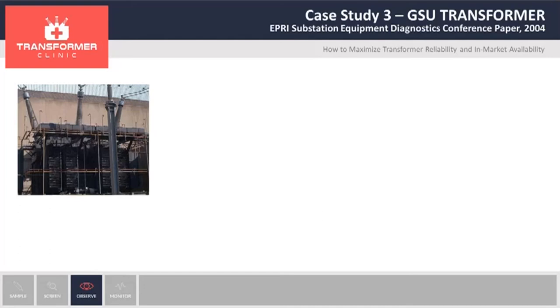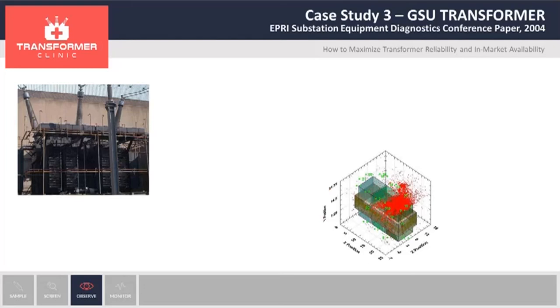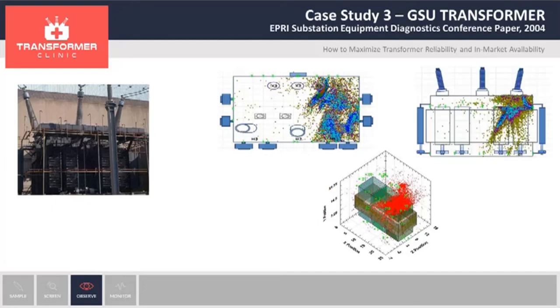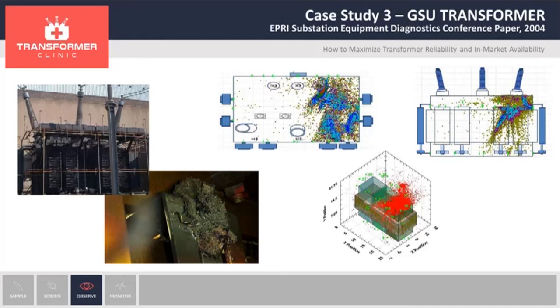We did the test and found the acoustic source on the upper right corner of the transformer. When looking at the top view, the red indicates the highest intensity of the fault — everything was concentrated on the X1 bushing. Looking at the front view of the transformer, everything is on the upper part. When they saw that, they decided to lower the oil and do an internal inspection on-site. They went inside, looked at the area where we found activity, and found the three copper busbars below the X1 bushing with carbonization. So there was a high temperature fault on that particular transformer. Signs of overheating were visible on the other two busbars — this was a matter of time before a catastrophic failure might happen.